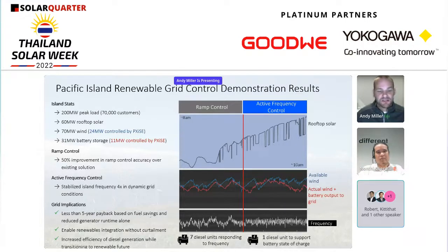The payback on this use case is less than 5 years on fuel savings alone. By reducing the number of diesel units required, we can also enable more renewable integration into the island and reduce renewable curtailment. This island was curtailing wind assets at 8 to 10% each year. With a more intelligent control solution using an energy storage asset, we could essentially eliminate that curtailment. So there's a really compelling case for using energy storage to improve the reliability of an island, with a very powerful economic case.